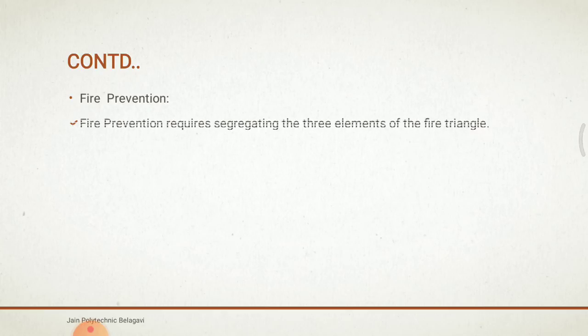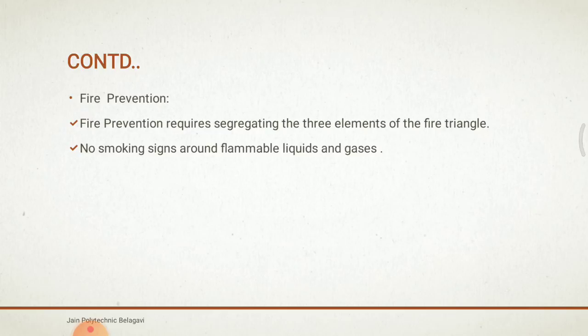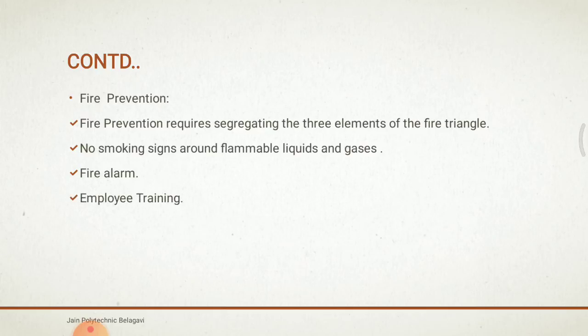Fire prevention requires segregating the three elements of the fire triangle. These three elements together form the fire, so in order to prevent it, these three elements are to be kept apart. In practice, a method of achieving this goal is to post and enforce no-smoking signs around flammable liquids and gases, and to have fire watches on all work involving a torch applied to materials for a minimum of two hours after the last torch is turned off.